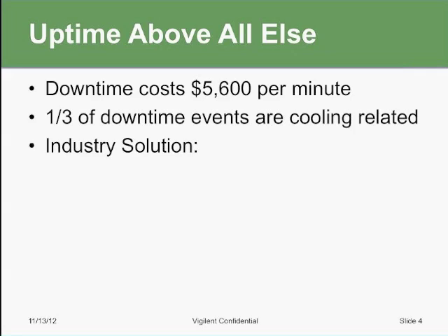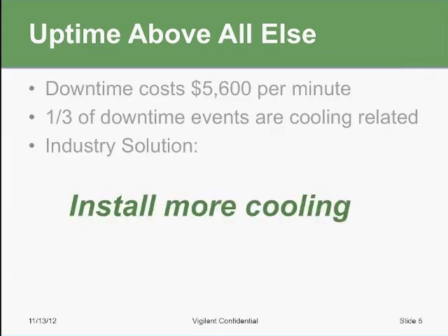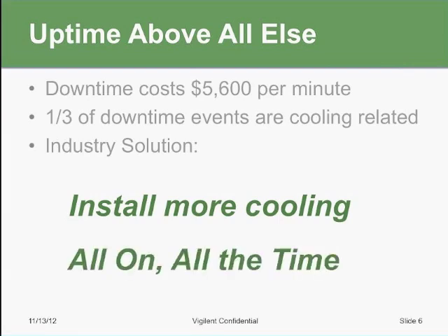And so the industry solution for mitigating this risk is two things. The first is to install more cooling capacity, to increase that headroom. And the second is to turn that cooling capacity on and leave it on all the time. And so this idea of redundancy is actually more specifically installed redundancy. And I'm going to make the point that installed redundancy is actually misguided. And not only is it misguided, but it can actually increase the risk of a downtime event. What is critical is operational redundancy, and there's a difference between installed redundancy and operational redundancy, which is important to understand.